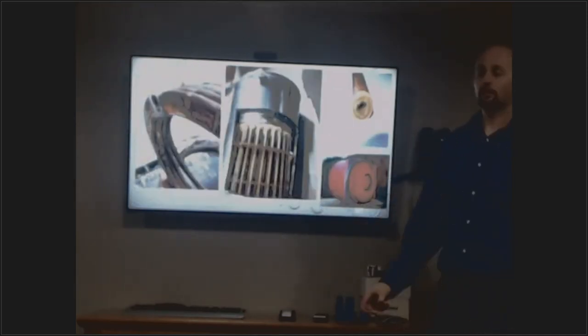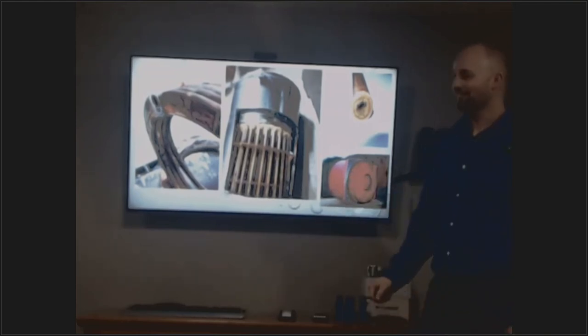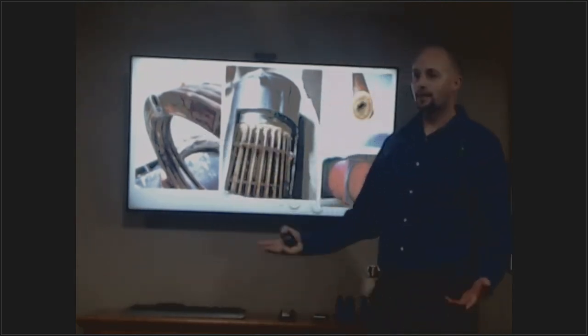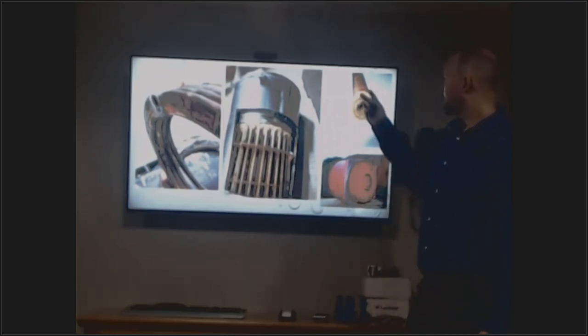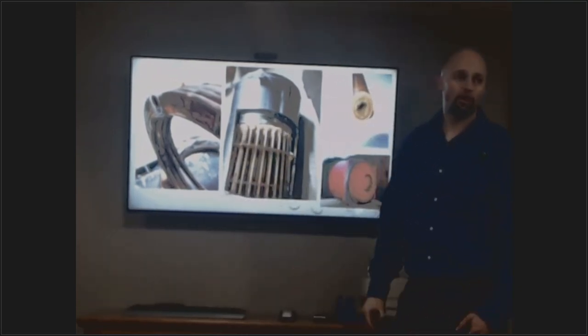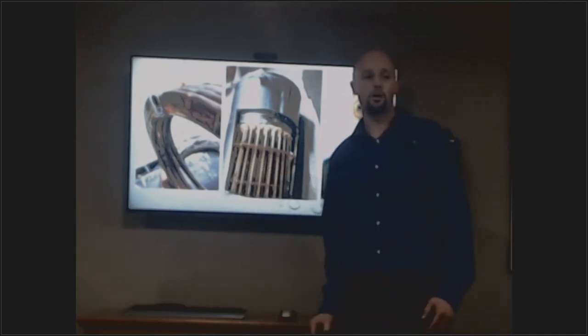On water quality: we've all pulled pumps out that look corroded and scaled. You get lime scale, calcium, magnetite, and other materials because we're mixing stainless, cast iron, copper, and brass — different metals that react with each other. In Park City, which was a mining town, there are a lot of minerals in the water. Throughout Utah we have very hard water, which creates havoc on closed-loop systems that recirculate the same water.